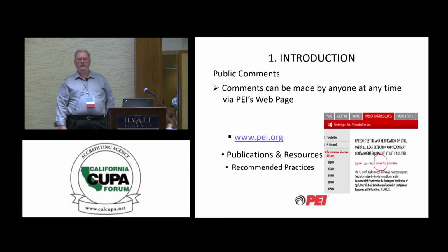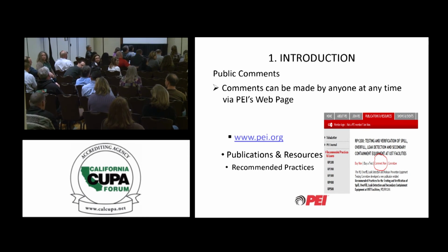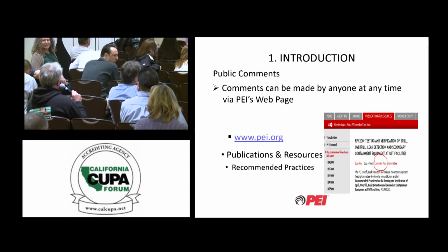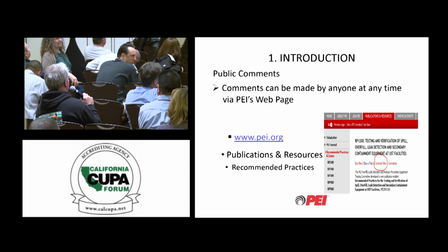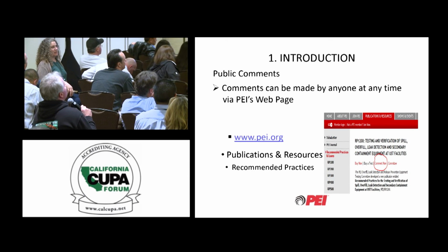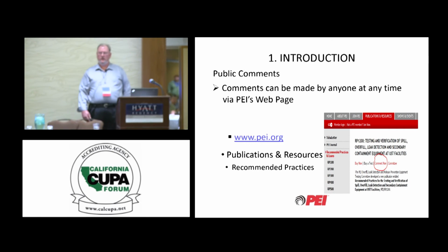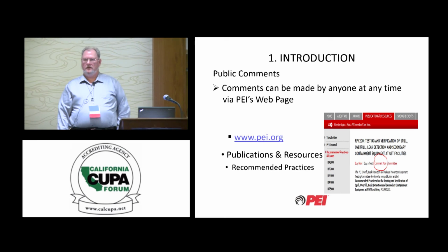We have one more question. It looked like on the spill bucket test, you were just addressing a one-size spill bucket, and if there's a larger spill bucket, like 15 gallons, does it matter? You're recommending it to be filled to the top? Yes, the procedure is not capacity specific. The procedure is to fill it up to 1.5 inches above, or to the top of the bucket. Without regard to the 5-gallon requirement?